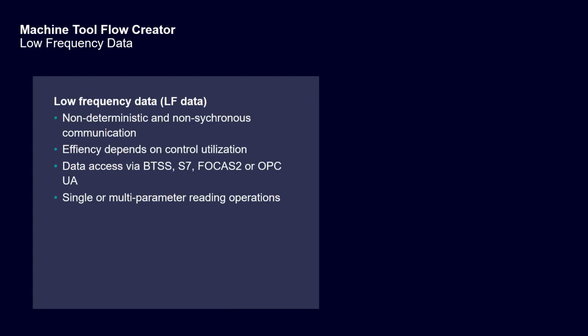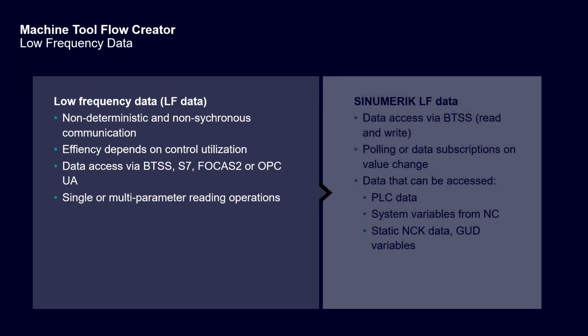Low frequency data is the term for the non-deterministic and non-synchronous communication. The efficiency depends on the control utilization, and the data access is done via the BTSS interface, the S7 protocol, FOCAS2 or OPC-UA. Low-frequency data can either be accessed by single or multi-parameter reading operations.